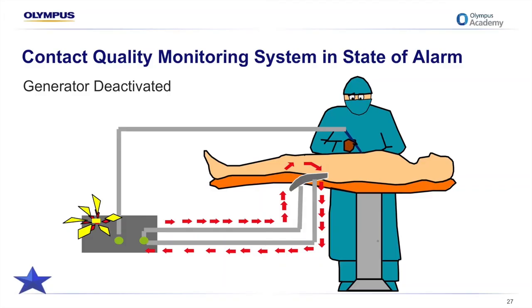This next slide shows a generator equipped with a contact quality monitoring system. Note how the return electrode and the patient interface has become compromised, thus creating the potential for a burn, as you just saw with the last demonstration. Before the burn occurs, however, a visual and an audible alarm is activated and the generator is immediately deactivated. Once again, I'll give you another demonstration of that now.